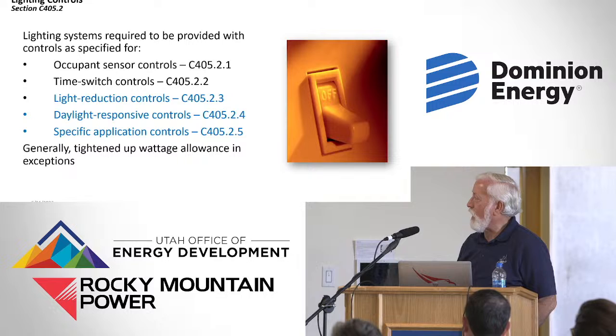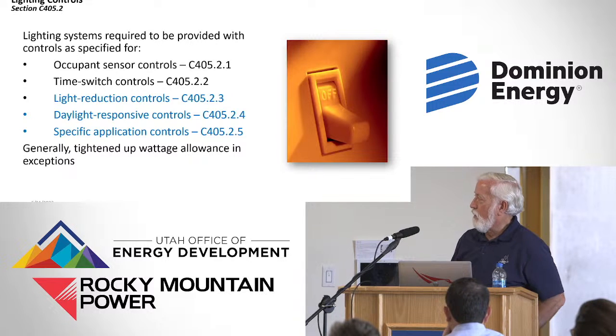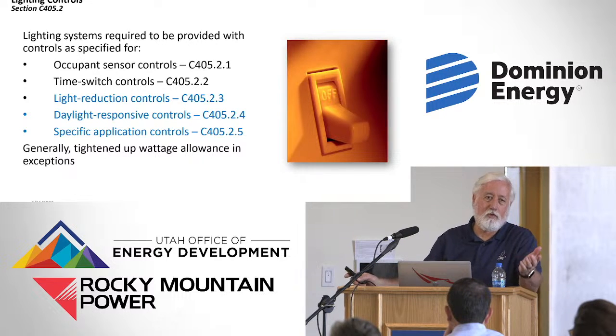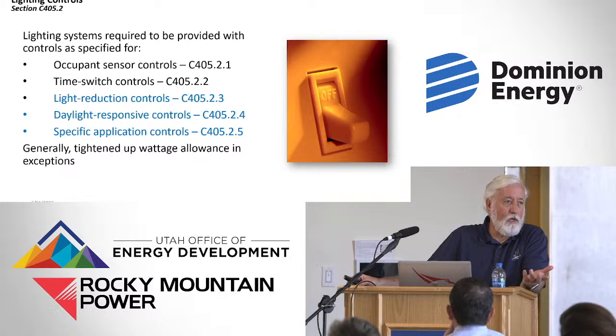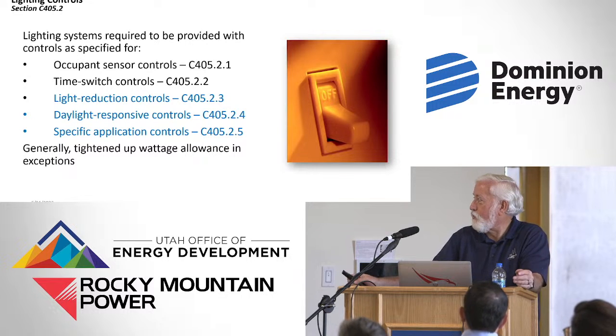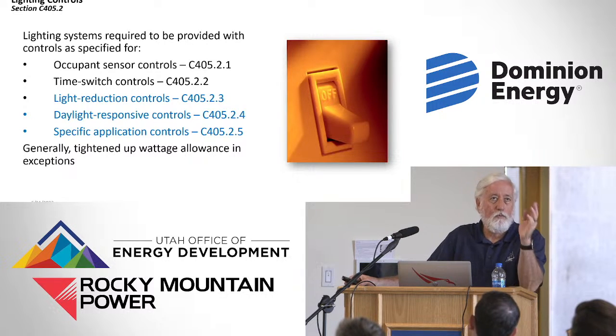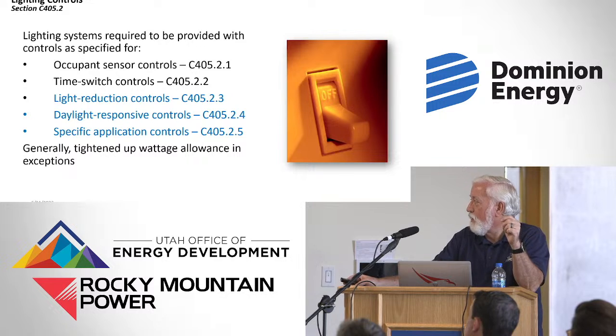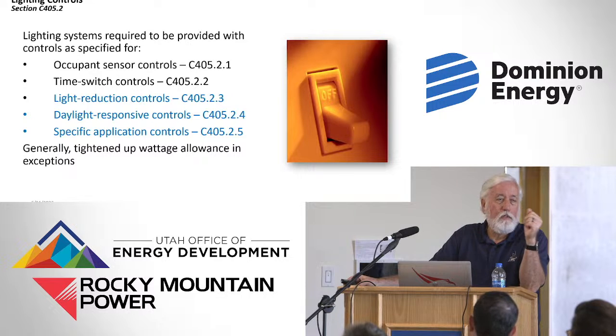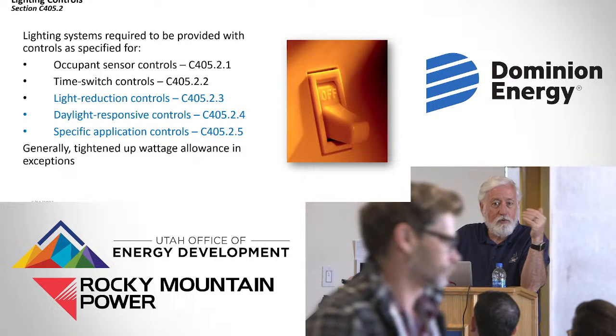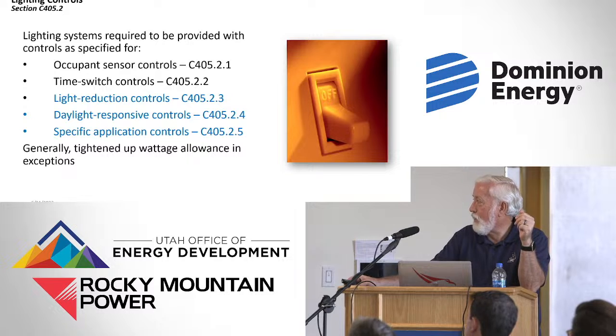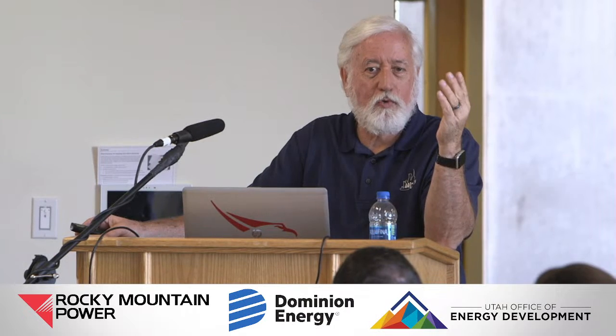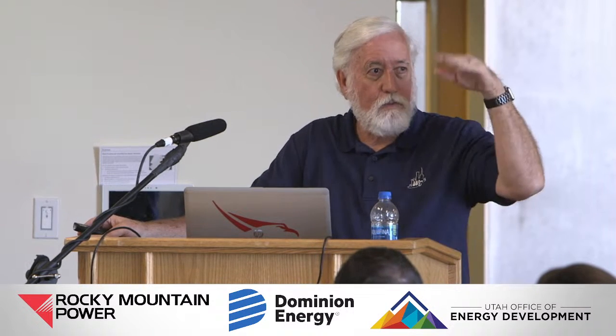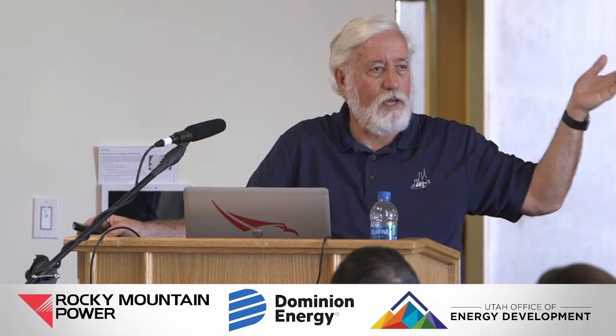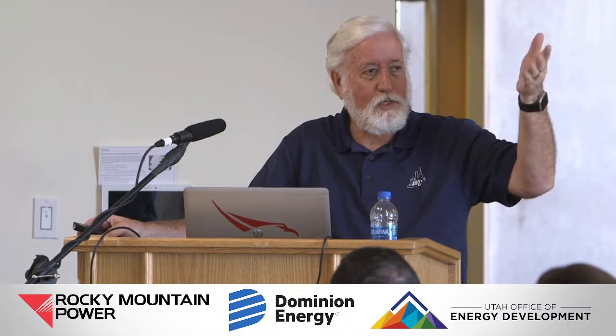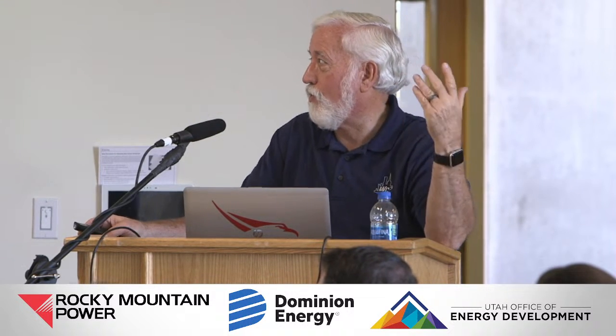So basically our lighting systems have occupancy sensor controls. You walk in, they turn on, or you leave, they turn off after so long. Time switch controls. We're programmed at certain times. Lighting reduction controls. You get some light through the windows, you reduce the lights. Maybe you've walked through a big box store, you notice the lights just changed. Well, enough light was coming through, it was sensed, and it reduced the lights. It might even turn them off almost.